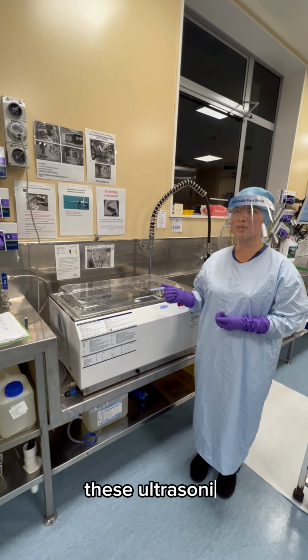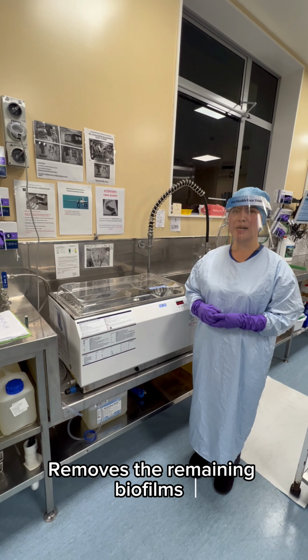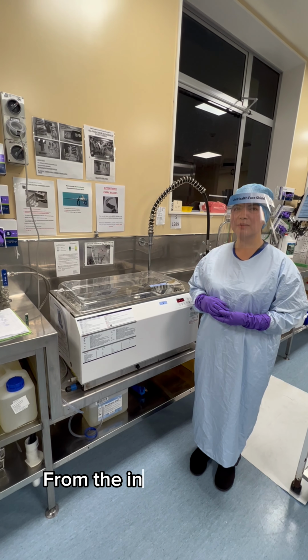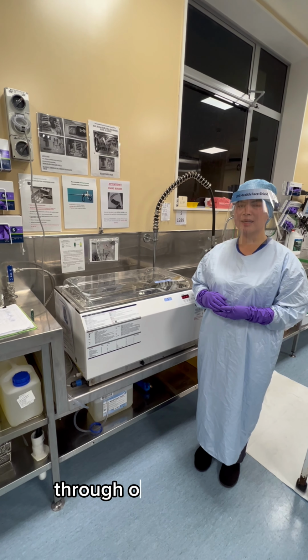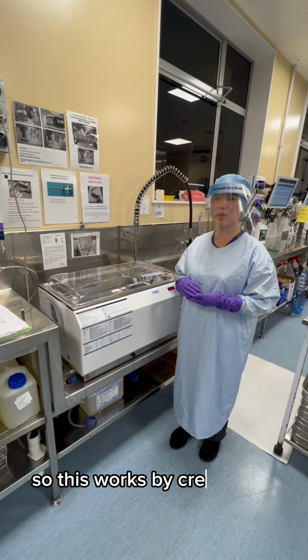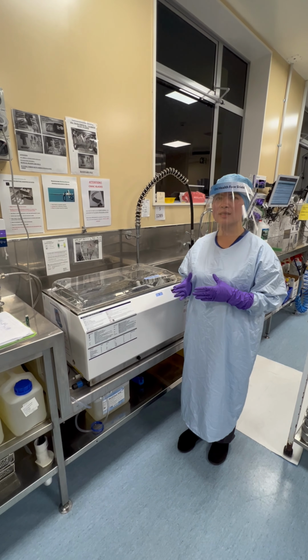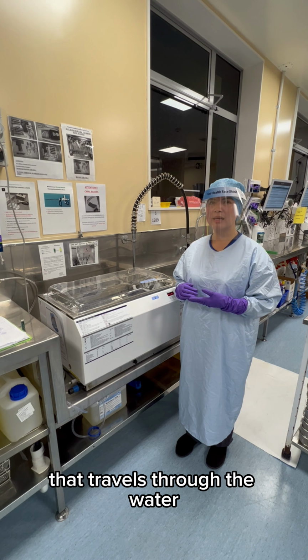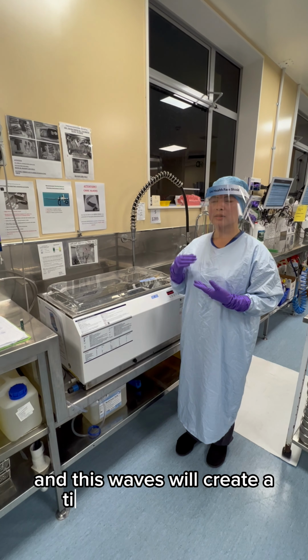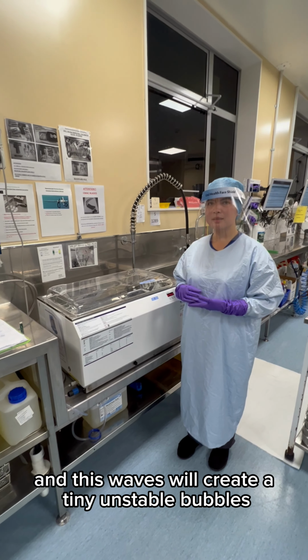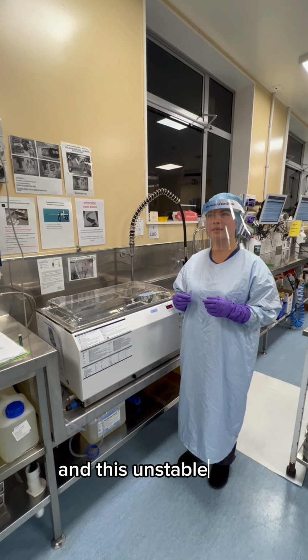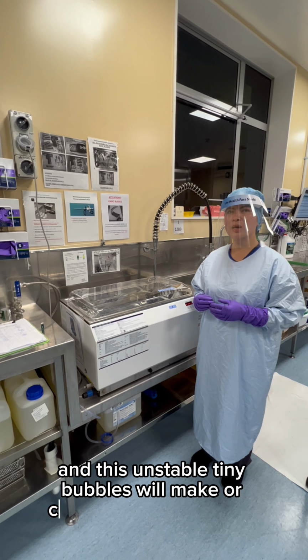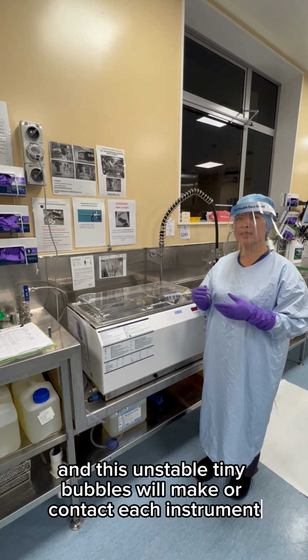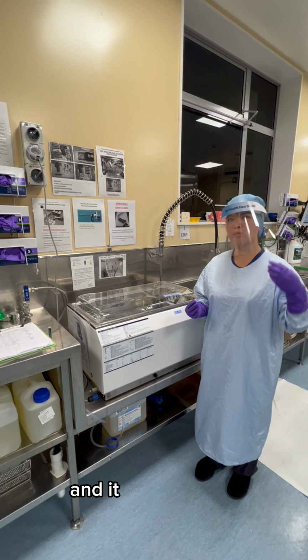This ultrasonic removes the remaining biofilms or any debris from the instrument that we cannot see with the naked eye. It works by creating ultrasonic waves that travel through the water, and these waves create tiny unstable bubbles, and these tiny unstable bubbles contact each instrument and implode.